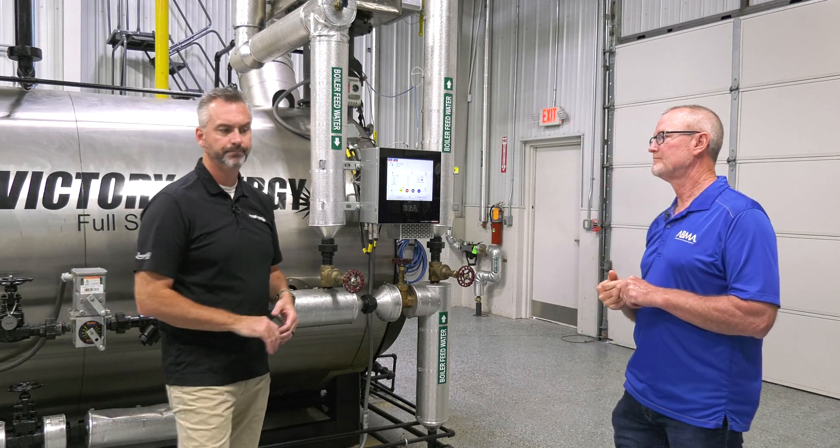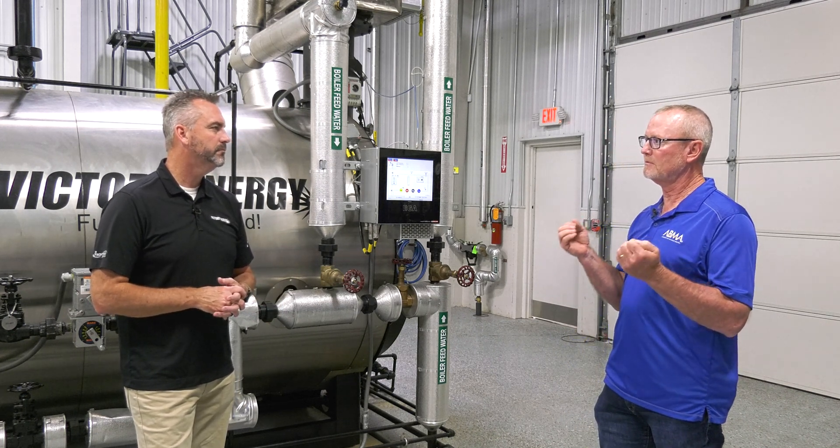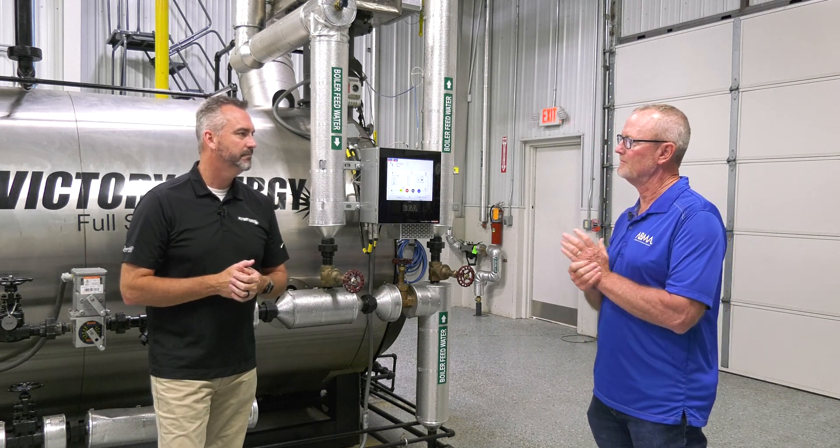A new operator in a boiler room is listening for that huffing sound. Most of the time it's harmonics — you just hear it. But every now and then you'll hear it repeatedly. We train maintenance guys to listen for things that are different. Walk through the boiler room, something sounds different — listen to it, see what it is, and then start looking to see what you can do to fix it. And obviously if it gets into a situation like that, certainly call a service company to make sure that the combustion is correct. Get that thing adjusted and get things right so you don't have a combustion issue you don't want to deal with.